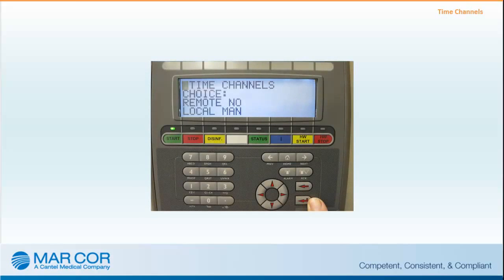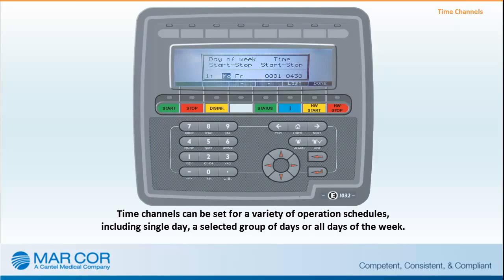The CWP can be operated in two different modes: auto start mode and manual mode. Auto start mode is the preferred method of operation as it allows for nightly heat disinfection and daily startup and shutdown of the RO. The auto start mode operates via time channels that allow for automatic heat disinfection of the RO, start, and stop based on times chosen for clinic operation. Time channels minimize operator interaction. If the CWP has been set to operate via time channels, the start time is typically set a minimum of 30 minutes prior to staff arrival, allowing for startup and a mandatory 15-minute rinse flush.